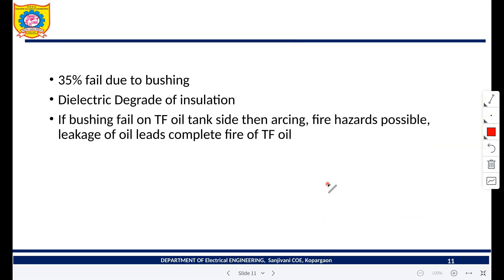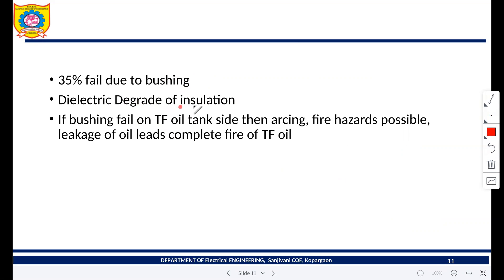35% of transformer failures are due to failure of bushings. Why do bushings fail? Because of dielectric degradation of insulation material. Dielectric degradation means the dielectric strength of the transformer bushing or porcelain is going to decrease.